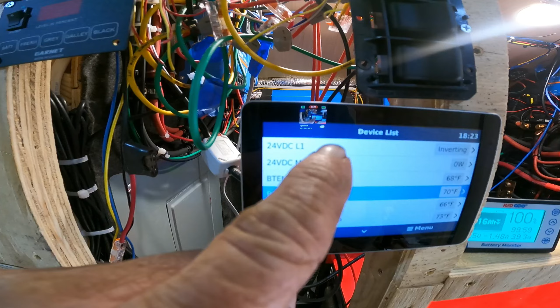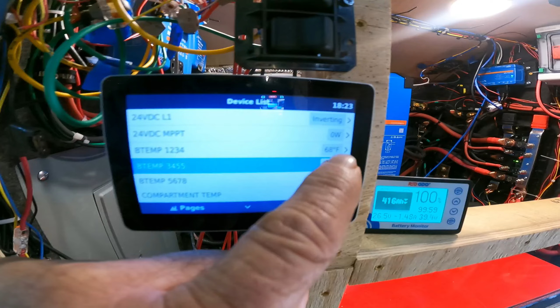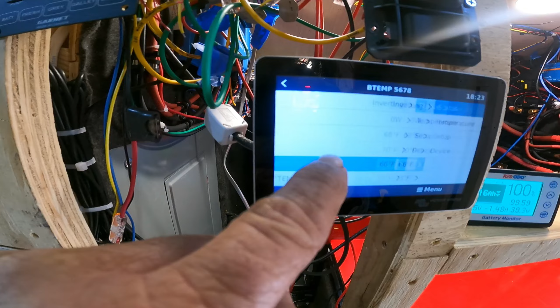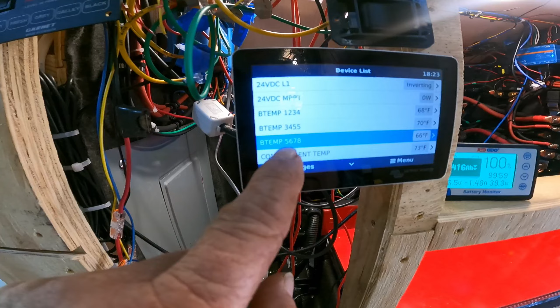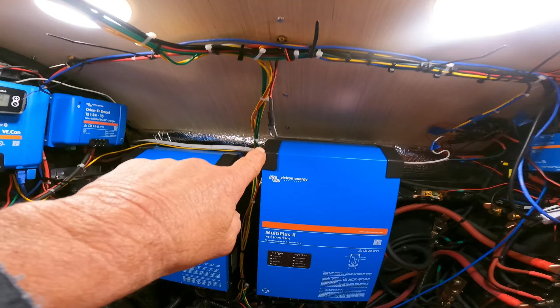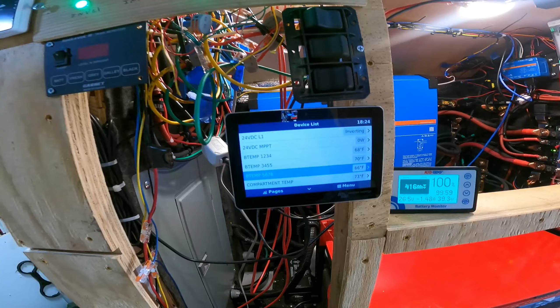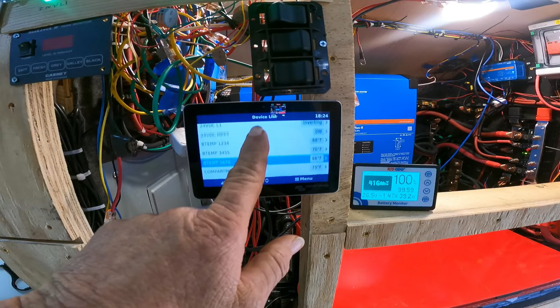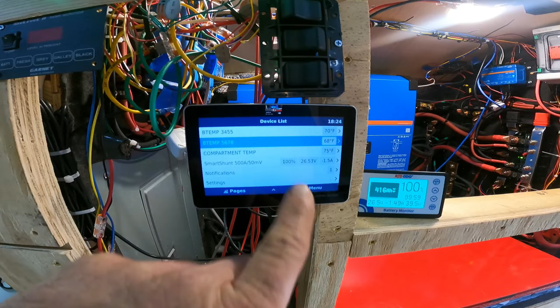I can't turn the other one on because I don't have the ability to configure it for split phase. Then I've got my 24 volt DC MPPT, not doing anything because nothing's connected. Then I've got my battery temperature for batteries 1,2,3,4 sitting at 68. Battery temperature for 3,4,5,6 should be 6... it's 70. Battery temperature for 5,6,7,8 is 66. And my compartment temperature is 73, which is this battery temperature right here. So they're all working, they're all registering, and I've got alarms set up for every single one of them if any one gets too high. For the battery temperature, it just sets off an alarm and lets me know. For the compartment temp, it actually turns on the fans.